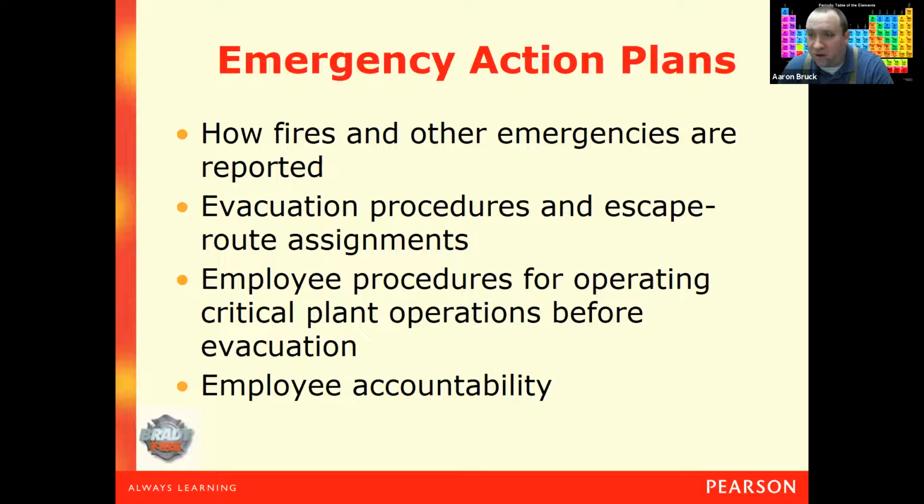And your instructor hits the emergency cutoff button just in case some of you miss it. That is one thing that you do so that there isn't a room filling up with natural gas in the event of a fire, for obvious reasons.